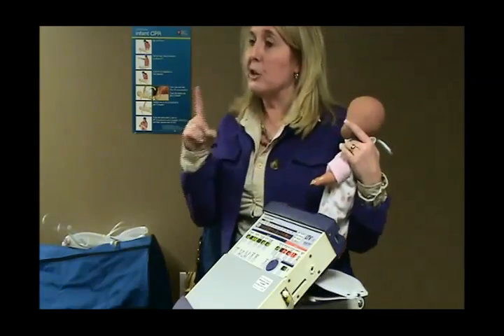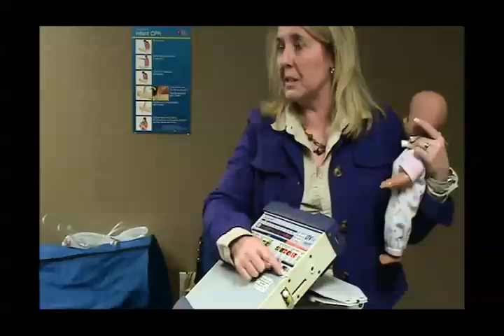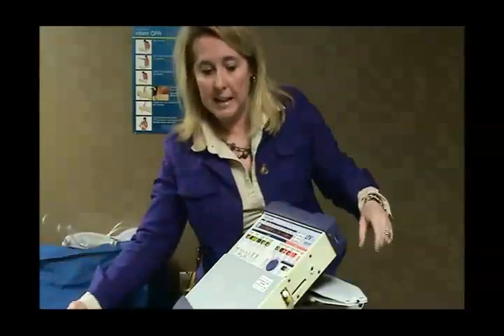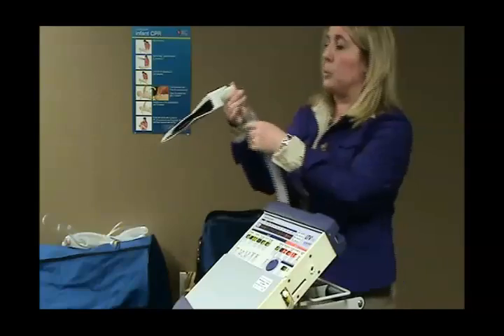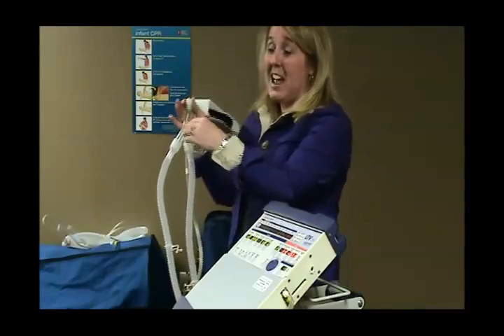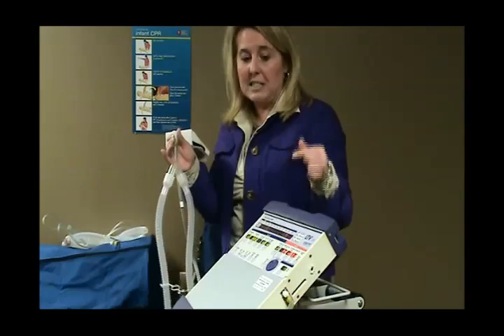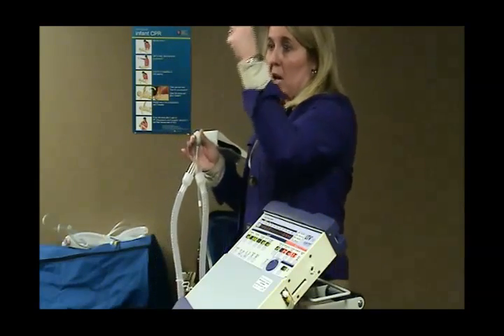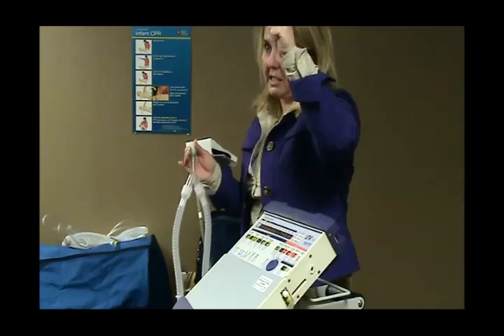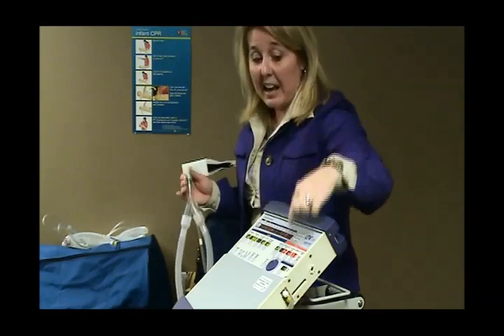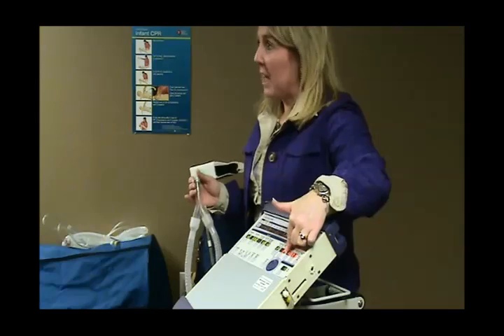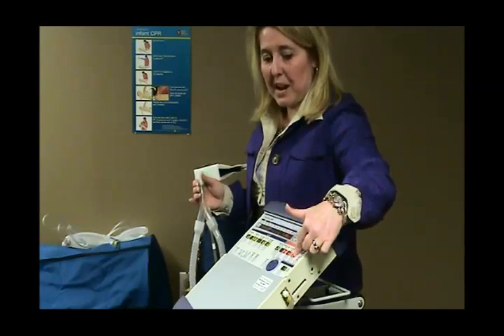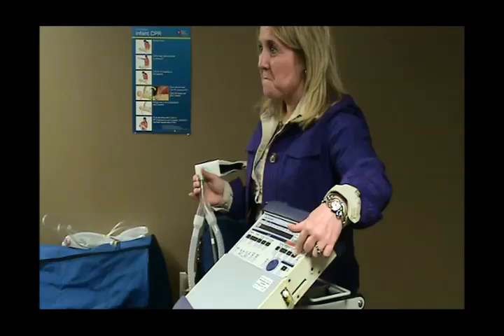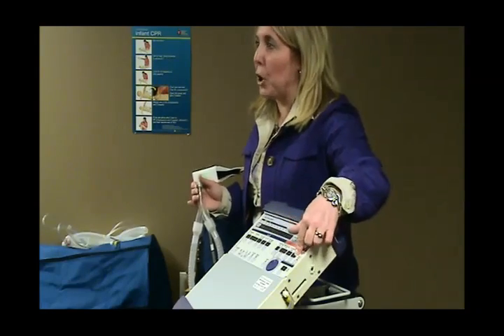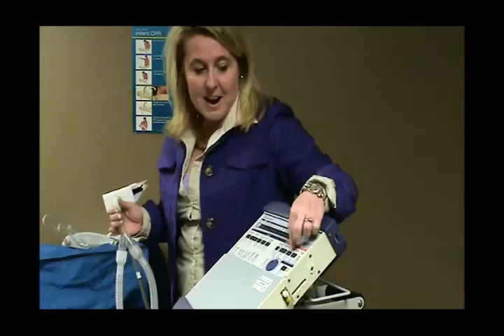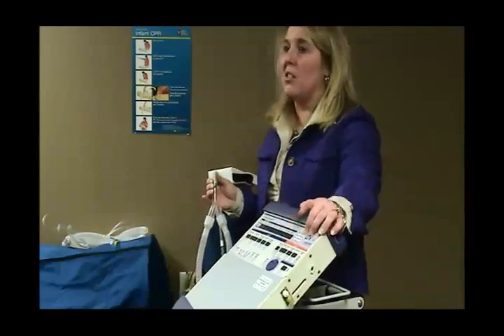Okay? So, here's the reason why you don't want to go messing with this. And actually in the training that we do at St. Louis Children's, we actually put a trach and a speaking valve on here and demonstrate it to people that you can actually disconnect the ventilator, have a tracheostomy tube flipping in the wind with a decannulated kid, and if this isn't set high enough, the vent won't alarm. Because we have this disabled, there's no air coming back through here, so we've disabled the low minute volume alarm so it didn't nuisance on us. And if we don't have that set high enough, the ventilator will not alarm.